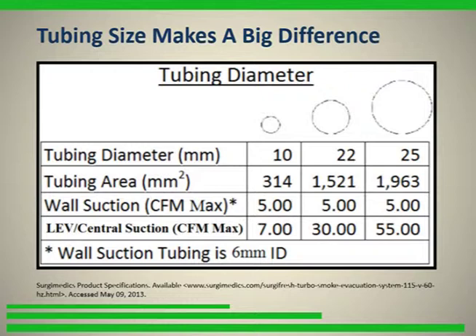That's obvious. But the important thing is the cubic feet per minute of airflow that you can get through these tubes, given wall suction, which is about 5 cubic feet per minute. If you attach it to a smoke evacuator, you can probably get up to about 11, maybe 15 cubic feet per minute. Whereas the other larger tubes, 22 and 25 millimeters, have pretty high airflow rates of up to 30 or even 50 cubic feet per minute. It should be pointed out, for effective smoke evacuation, at least 22 cubic feet per minute is needed, preferably 25 to 35 cubic feet per minute. Does a great job of capturing not only the smoke, but the ambient air above the smoke, which really serves to push the smoke toward the collection site.